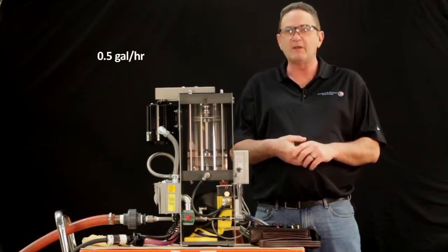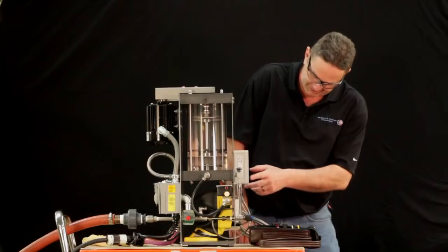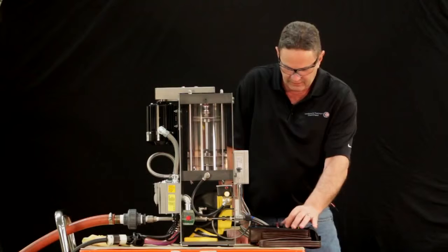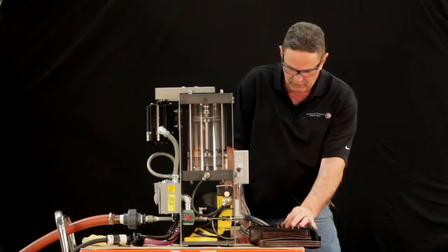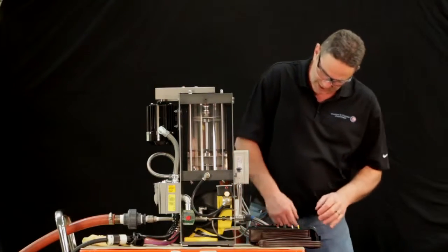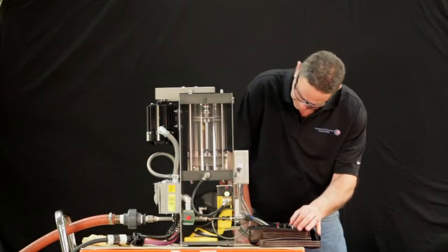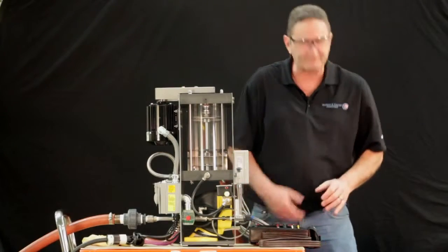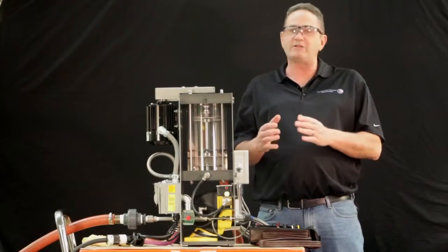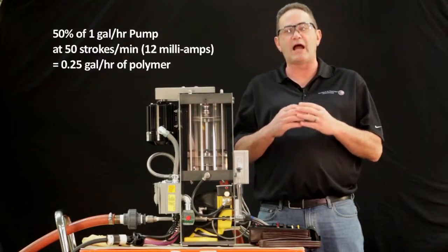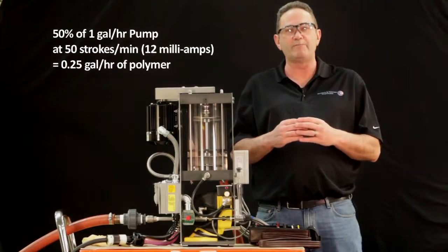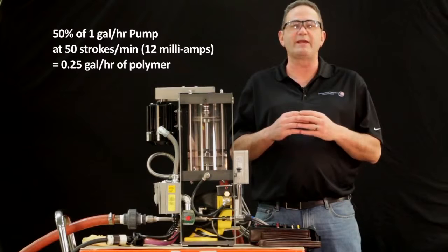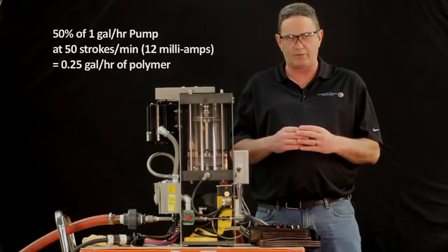on the pump. My recommendation would be to simply take your strokes from 100 and adjust it to 12 milliamps, which is 50 strokes per minute. We have now taken that half gallon an hour in the neat polymer pump, and we have now cut it back to a quarter of a gallon in the neat polymer pump.